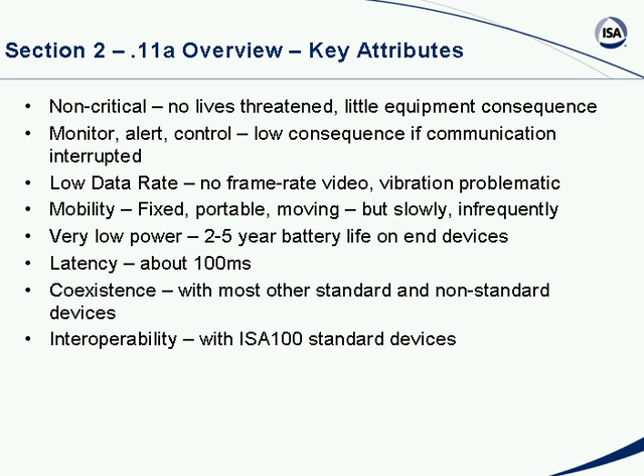It will support mobility — fixed devices, portable devices, or moving devices — but the decision was made that these devices would move slowly and infrequently, as a compromise on the overhead of keeping track of the routing table. It's primarily for fixed and portable operation, with some slow-moving device support. It has to be very low power — in a typical application it will last longer than five years; we say two to five years here. If somebody turns on their vibration sensor frequently it will cut that battery life down, but the design target is five years or better. Latency will be around 100 milliseconds, which the end user community has said is acceptable for the process business.